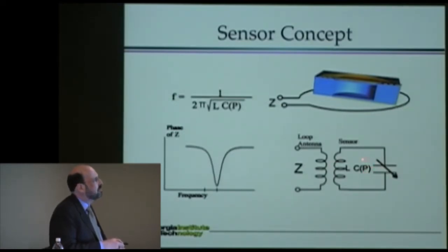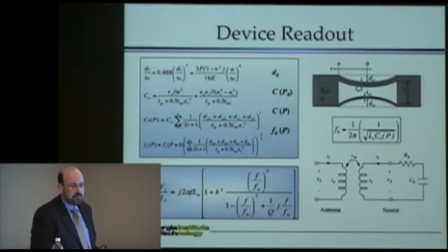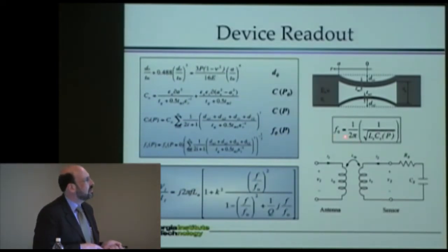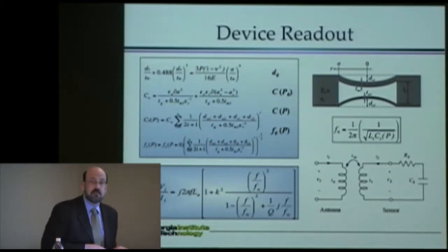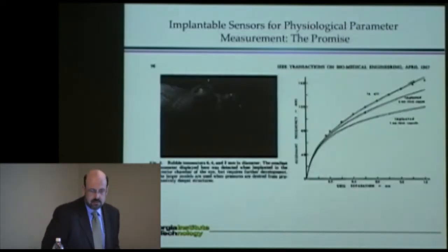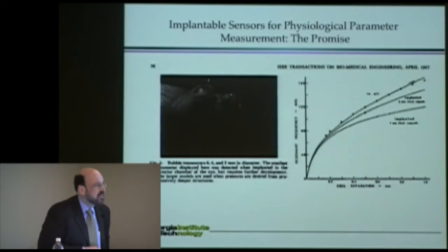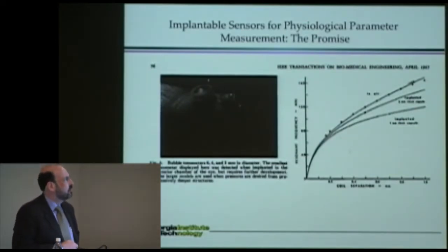As the pressure changes, the resonant frequency of this changes, and I can read it out with an external loop antenna. And if I know something about the mechanics of the device, then I can trace this frequency that I read out all the way back to what that deflection must have been, and then from that, what the pressure must have been on the device. That's basically the concept. Now, it turns out that this device works quite well.